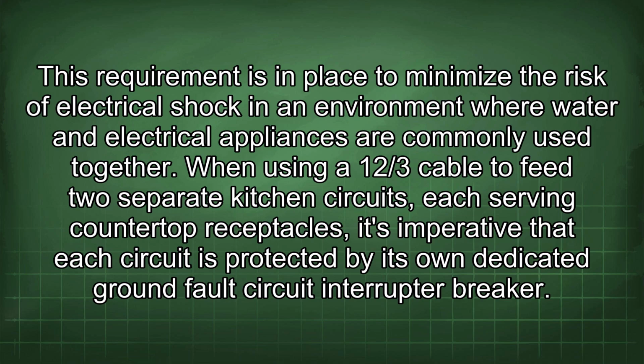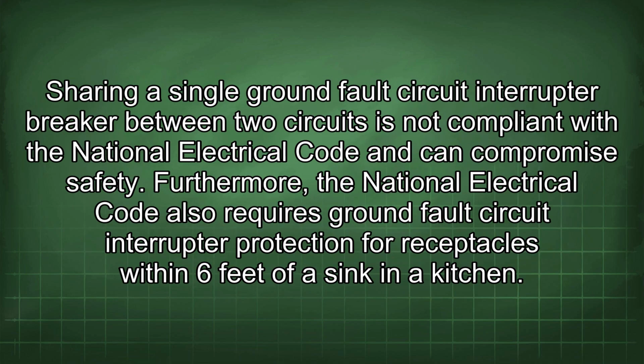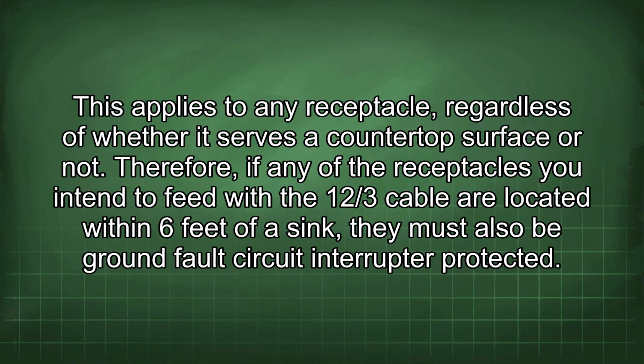When using a 12/3 cable to feed two separate kitchen circuits, each serving countertop receptacles, it's imperative that each circuit is protected by its own dedicated ground fault circuit interrupter breaker. Sharing a single ground fault circuit interrupter breaker between two circuits is not compliant with the National Electrical Code and can compromise safety. Furthermore, the National Electrical Code also requires ground fault circuit interrupter protection for receptacles within 6 feet of a sink in a kitchen. This applies to any receptacle, regardless of whether it serves a countertop surface or not.